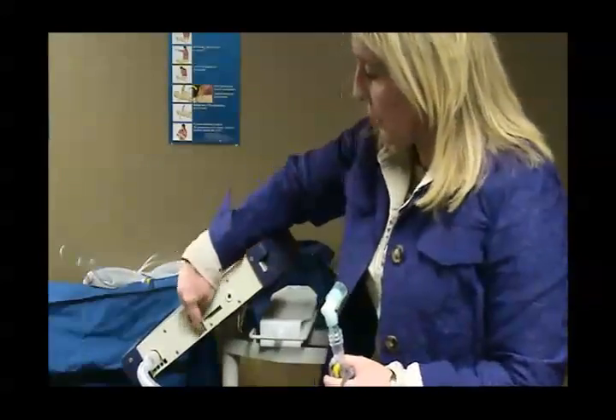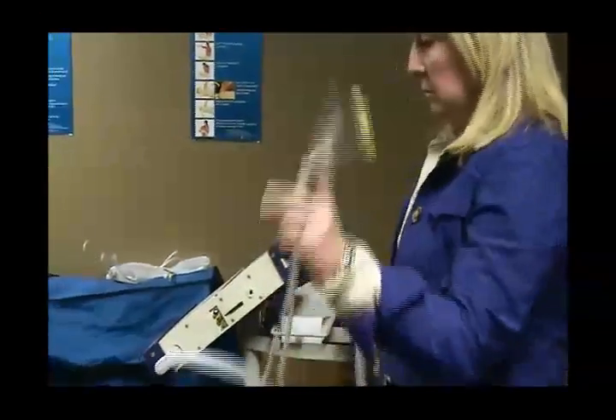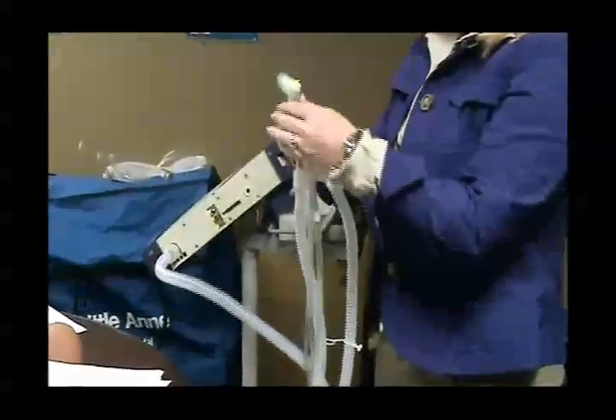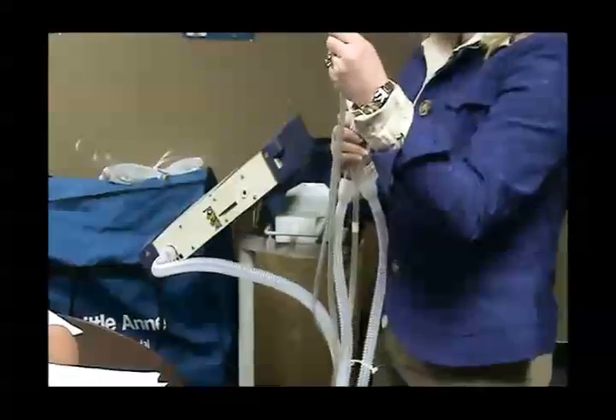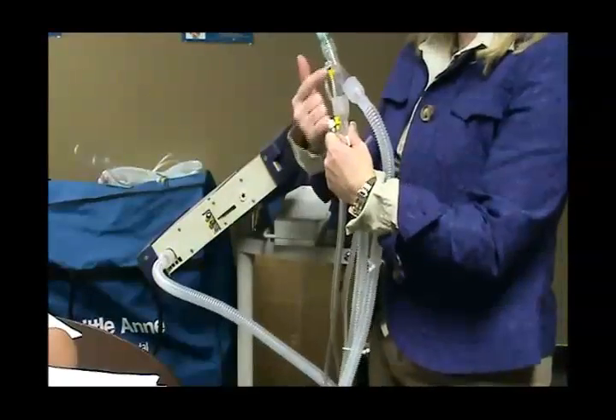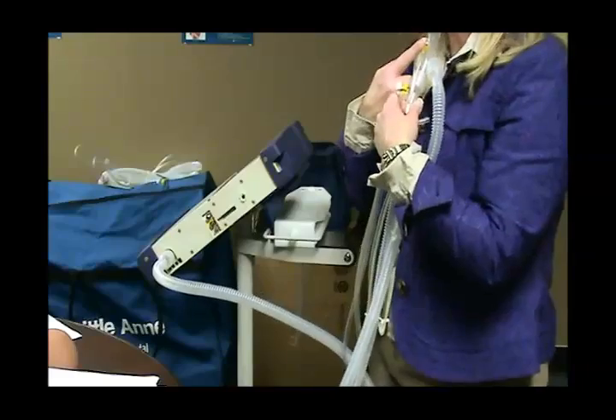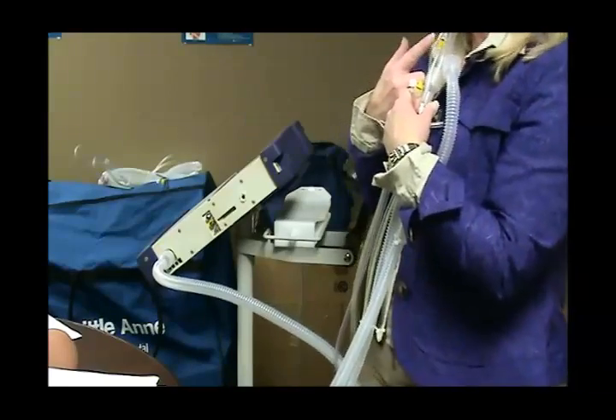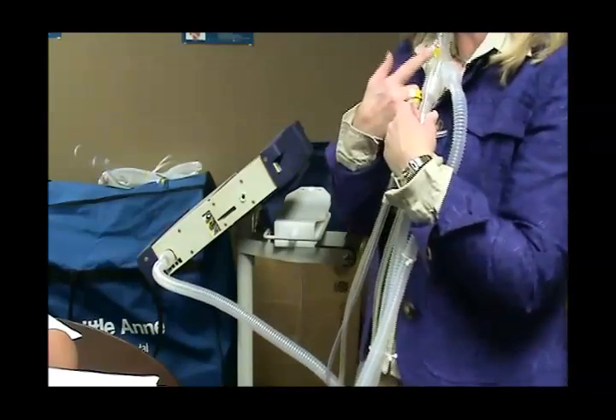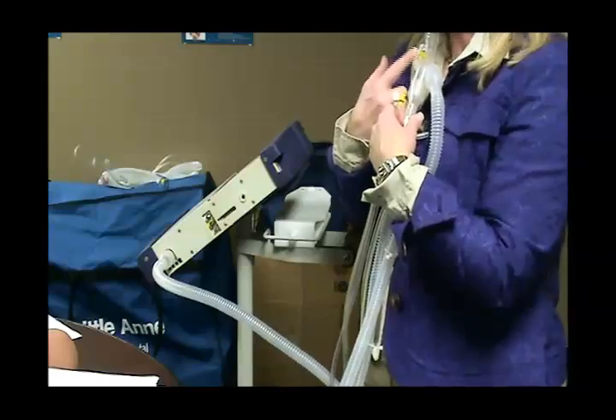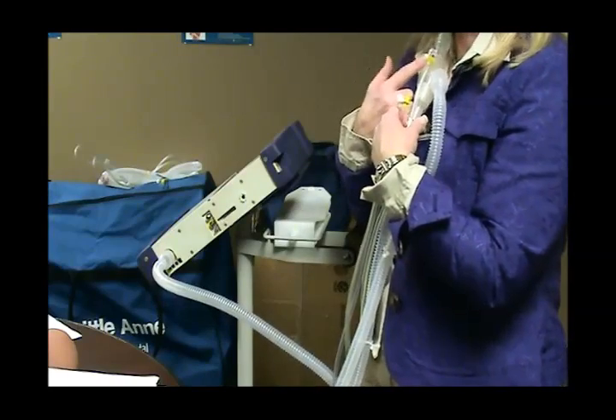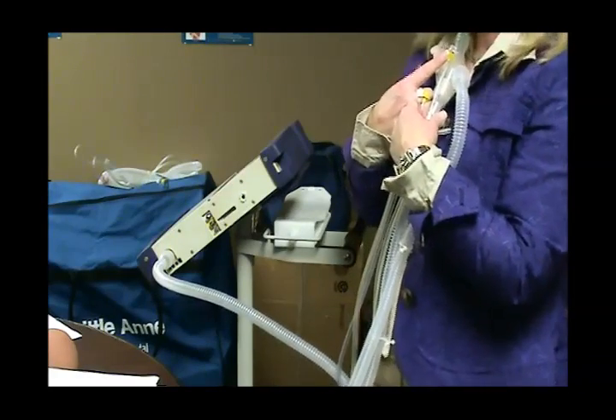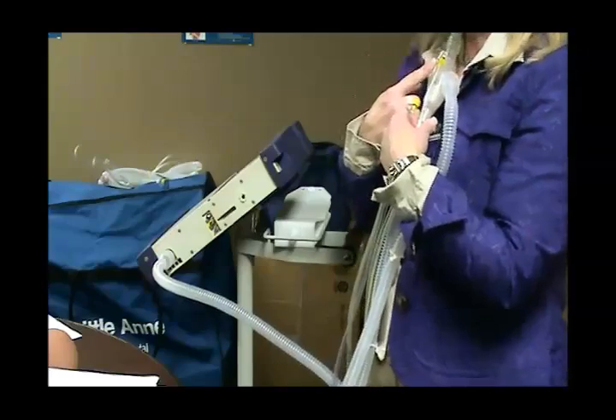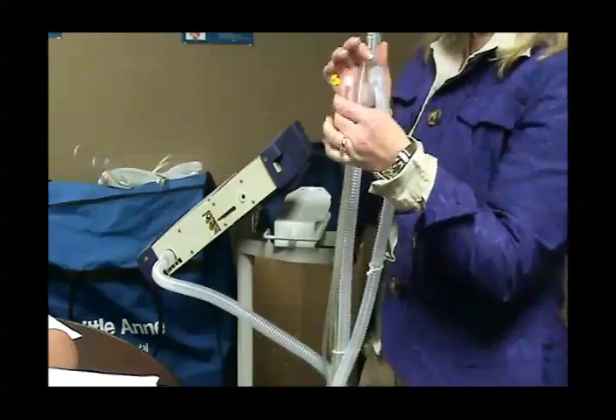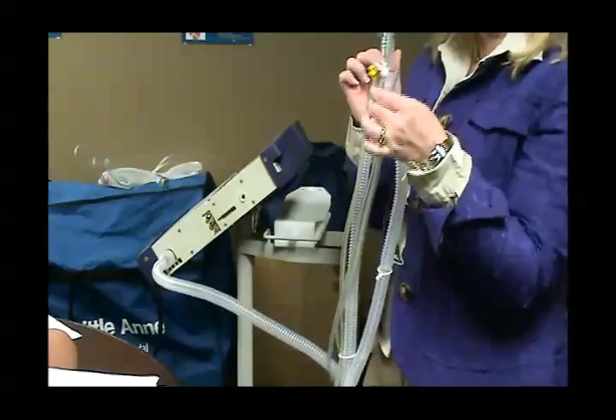You have 3 other holes. You have 3 other tubings. These are your flow tubes, okay? If you trace them back, they go right up here to the airway. This is what makes this ventilator a very sensitive ICU type vent. It directly measures flow and pressure right at the patient's airway. Doesn't estimate it, doesn't guess, it measures it, okay? So it's going to work just like an ICU vent.